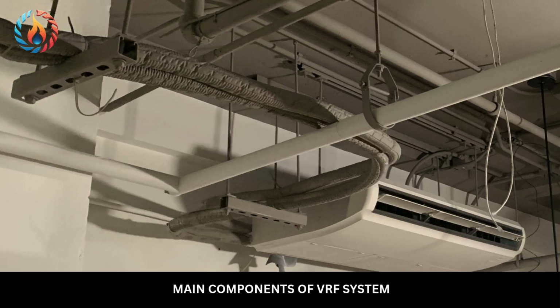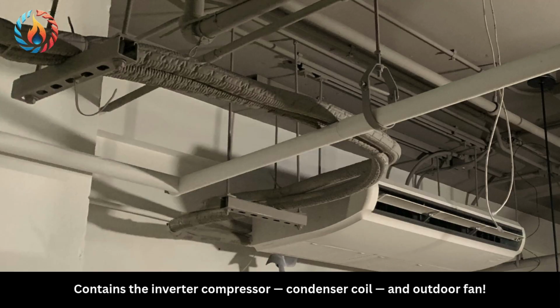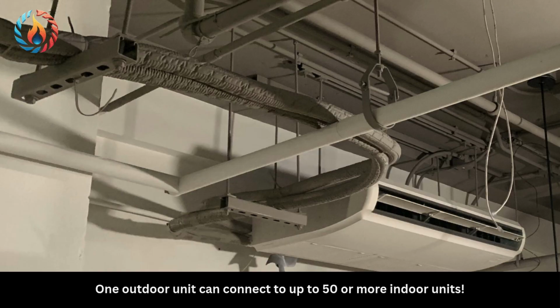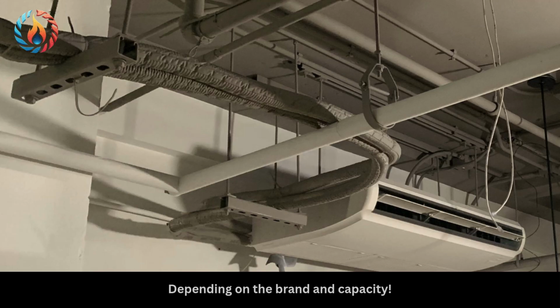Main components of VRF system. Guys, let me quickly explain all main components. Component 1, outdoor unit. Contains the inverter compressor, condenser coil, and outdoor fan. One outdoor unit can connect to up to 50 or more indoor units, depending on the brand and capacity. Component 2, refrigerant branch controller. This is unique to VRF systems. It is a junction box where refrigerant pipes branch out to individual indoor units.